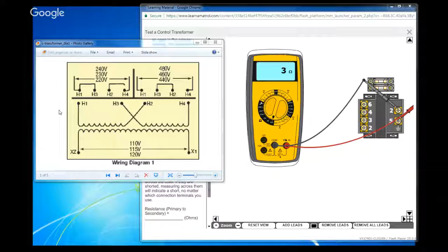Now, if we want to use a lower voltage here, notice the configuration jumpers are different. We have an H1 to H3 and an H2 to H4 jumper. Okay? And if we look at that, we'll see that H1 and H3 here will be jumpered. And if we follow that out, we'll see that we actually have a series parallel combination of windings. So now we actually have two primary windings hooked in a parallel configuration to drop it to 110 volts.